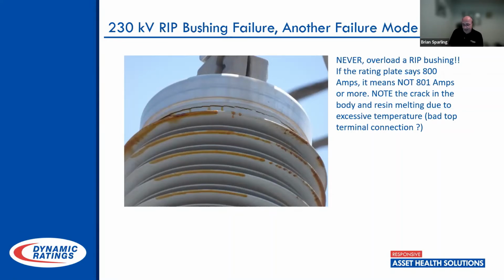And here's what can happen. Now, there's some conjecture about what happened here, but in this case, the top terminal of this bushing overheated. Some people say it was dissimilar metals. Some people said it was a bad connection, or no, you just overloaded the transformer. That's where the lawyers got involved. But you can see here, this did overload, and it cracked at the top. And that brown goop you see is the resin melting inside at the top and coming out. So this bushing failed. The good news is that it did not blow apart, so to speak. It failed quietly, but it failed nonetheless.